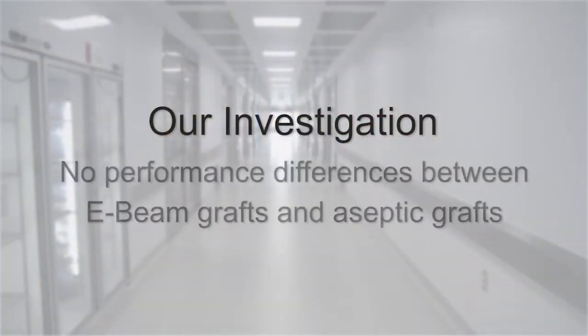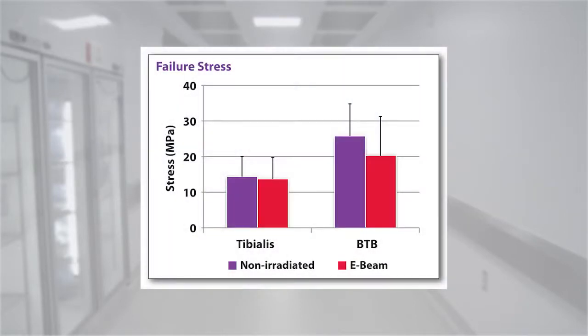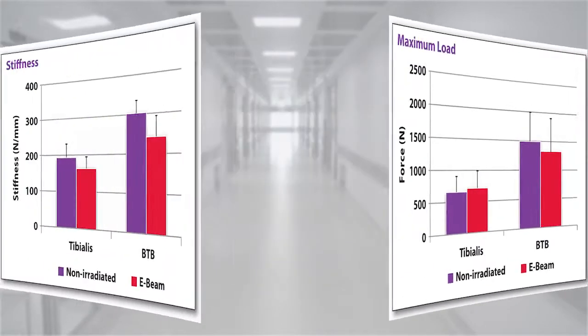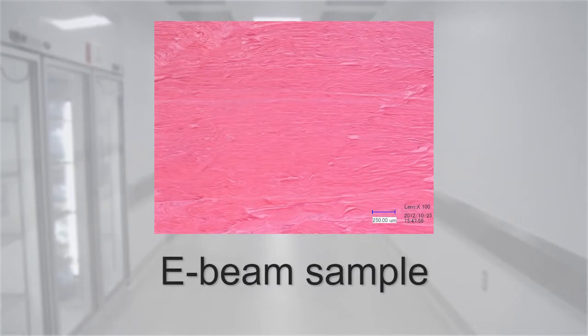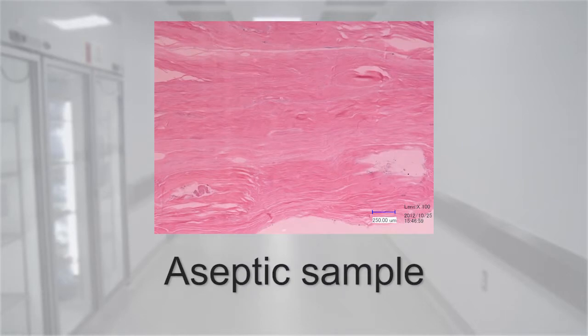And we found overall that there were no differences between the electron beam sterilized grafts and aseptic grafts. We also looked at the structure of the collagen using histology, and we found that there were no differences in collagen fiber alignment, spacing, or diameter between the electron beam sterilized tendons and the aseptic tendons.